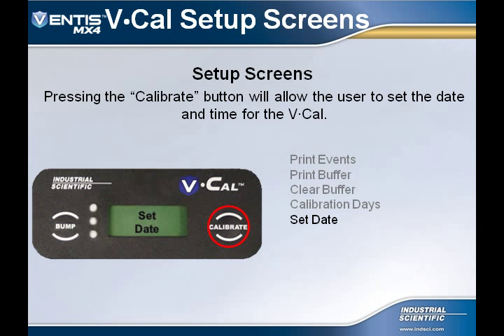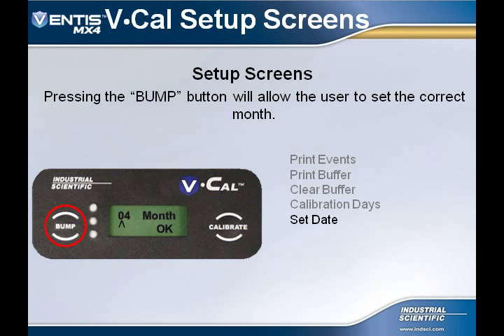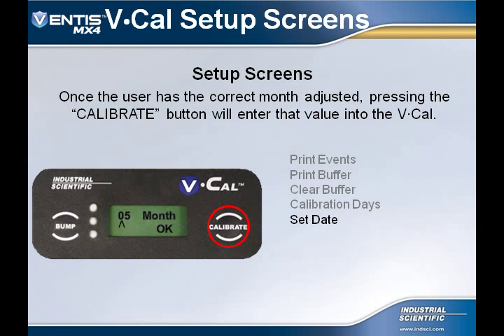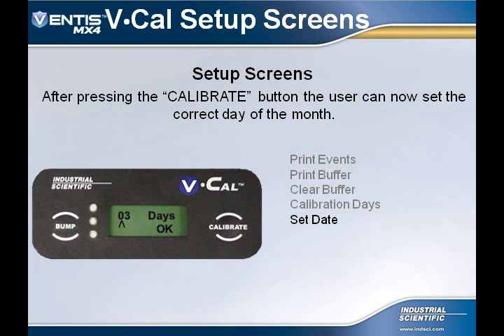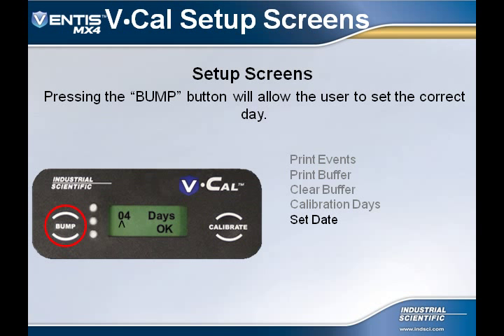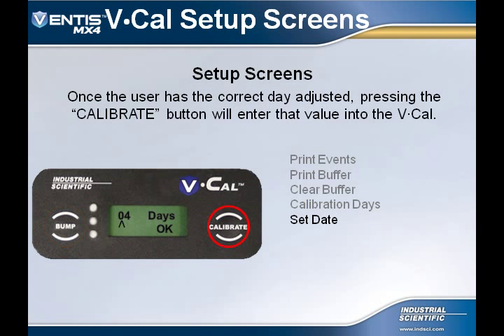Pressing the calibrate button will allow the user to set the date and time in the VCal. After pressing the calibrate button, the month will be displayed. Pressing the bump button will allow the user to change the value for the month. Once the correct month is adjusted, pressing the calibrate button will enter that value into the VCal. The next screen is to set the current day of the month. Pressing the bump button will allow the user to set the correct day. Once the correct day is adjusted, pressing the calibrate button will enter that value into the VCal.